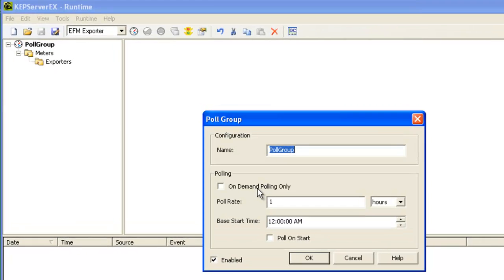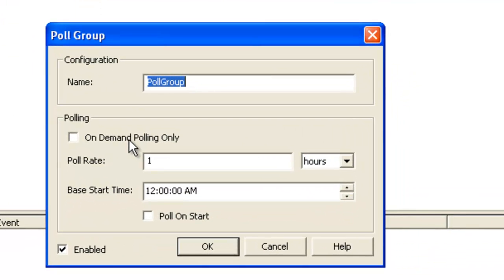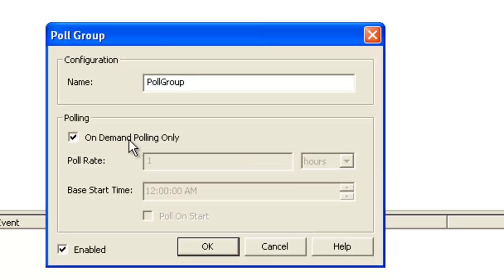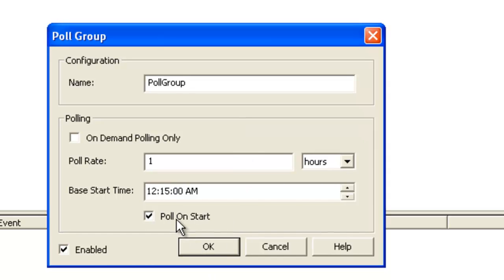So if we look at the poll group settings, each poll group exposes a poll tag, which when written to, will trigger a poll, so we can operate in an on-demand only mode. We can also have the server schedule polls. So with this configuration, we would schedule a poll 15 minutes past the hour, every hour. We also have an option to poll on start.